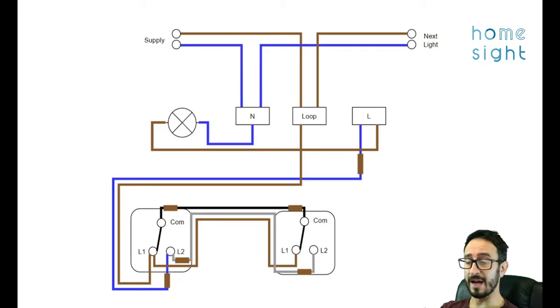Now this is how a UK standard, and I say standard, there's lots of different standards sometimes, this is one of the standards of a UK lighting circuit with two-way switching. We've got a supply coming in with our neutral on blue and our brown live and that's coming into a loop and out again onto the next light. Our neutral here you can see is going straight to our bulb and our brown live is coming through to a switch live here.